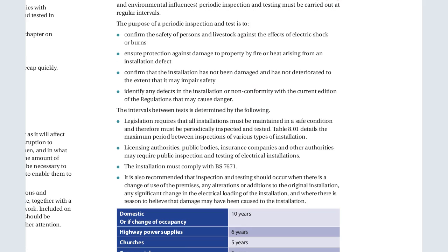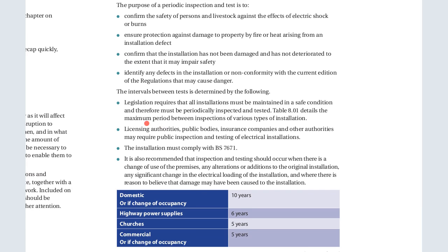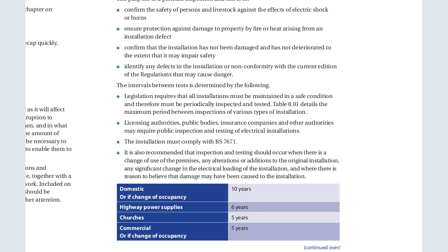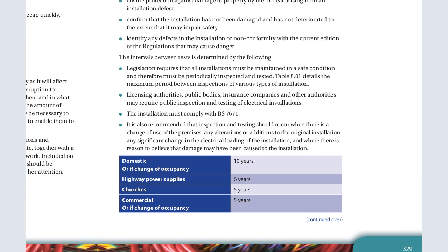Another one is to confirm that the installation has not been damaged and has not deteriorated to the extent that it may impair safety. Another one is to identify defects in the installation or non-conformity with the current edition. Now we have the intervals. The intervals between the tests and inspections are the following. The legislation requires that all installations must be maintained in a safe condition and therefore must be periodically inspected and tested. So Table 8 below gives the maximum period between inspections for various types of installation.